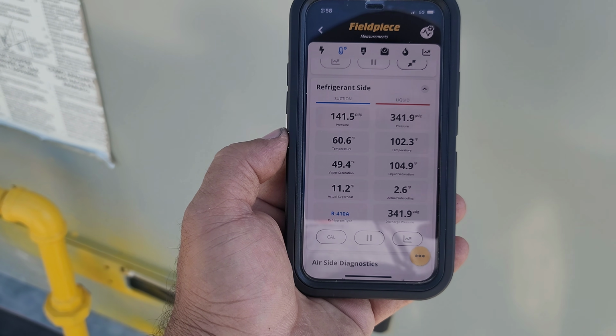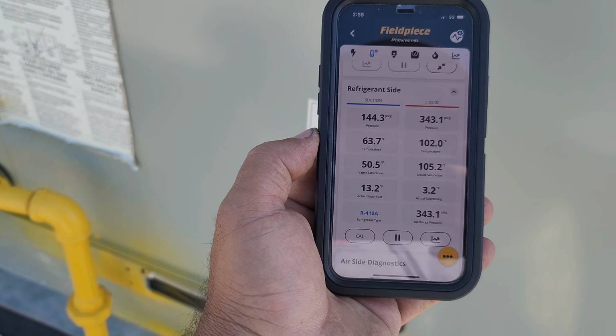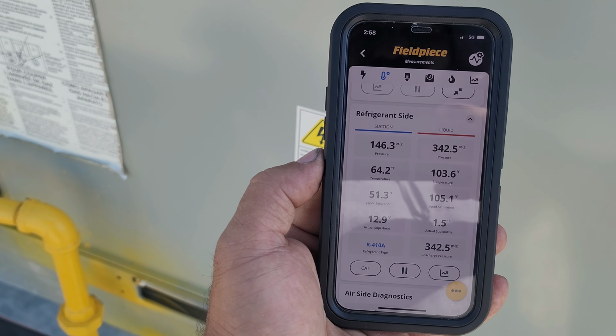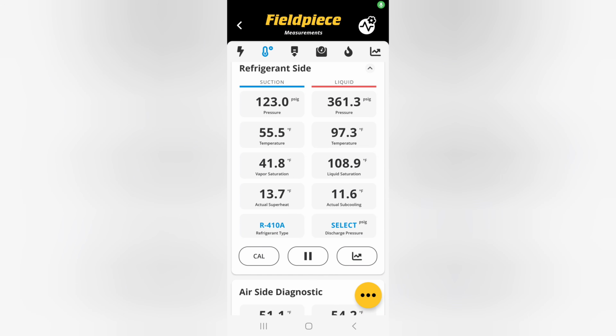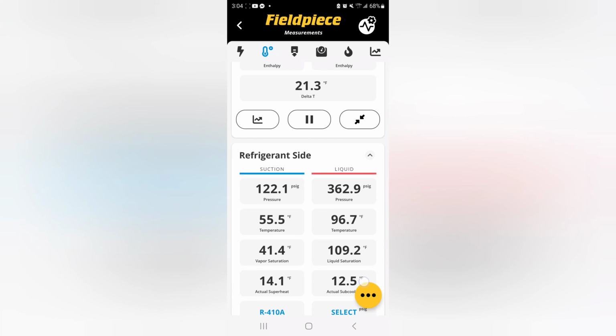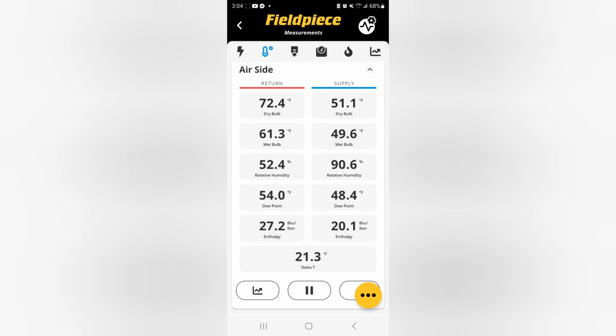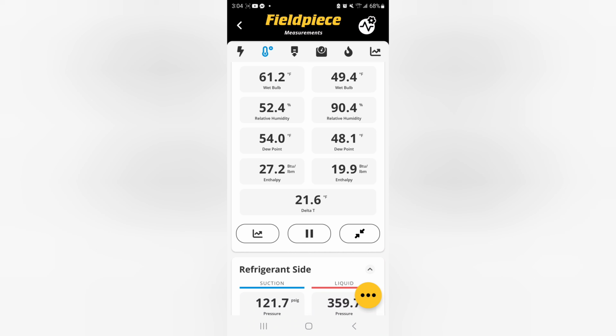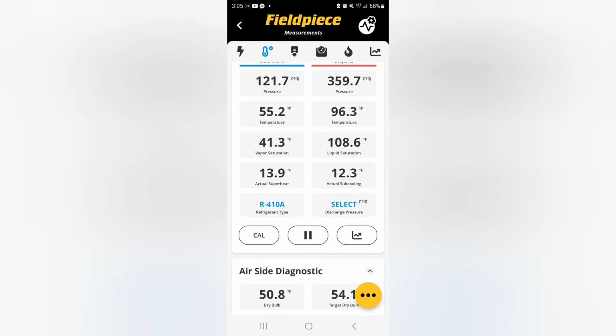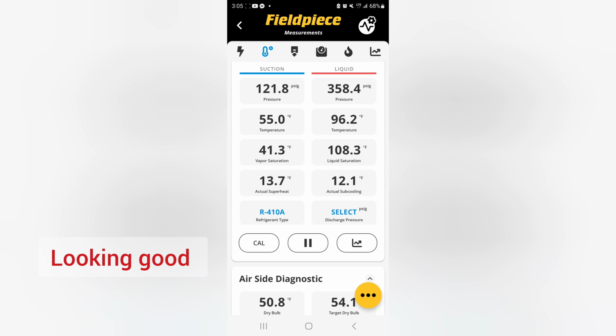So checking on our subcooling and superheat. Let's give it 5 minutes. Okay, so our readings are looking good. Actual subcooling is 12 approx, and the superheat is 14.1, and the air side diagnostic is also looking okay. So dry bulb 72 return air, supply air dry bulb 50. That's the mixed air, you can say, because the economizer is closed. So 100% return air. So readings are looking good for first stage.